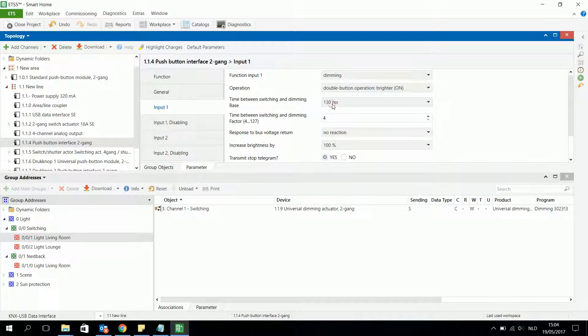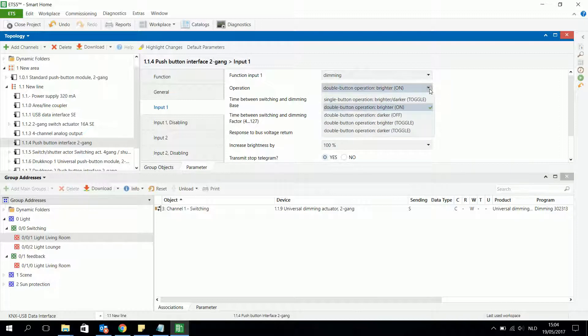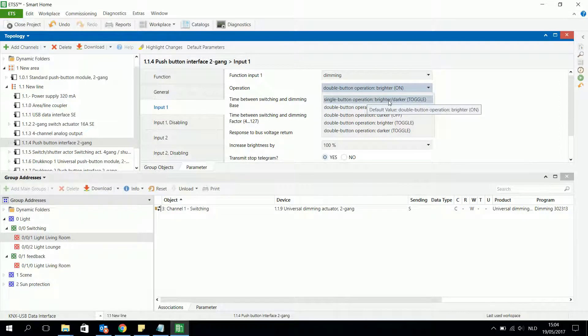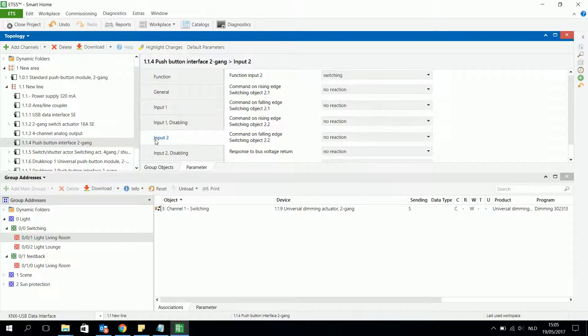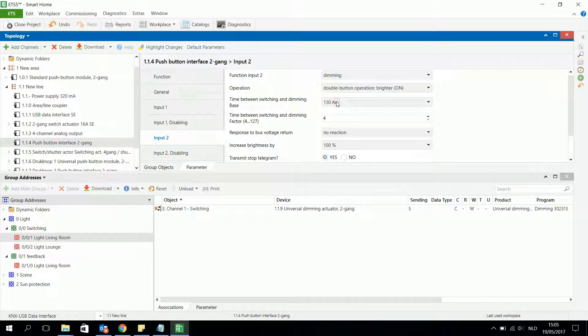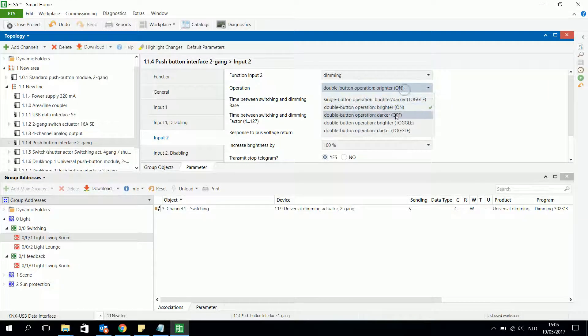I can choose dimming instead of switching. For input 1 I choose to dim the light. I can choose toggle with input 1 — making the light brighter and darker or on and off. Alternatively, input 1 can make the light brighter and on, while input 2 with the dimming function can make it darker and switch it off.